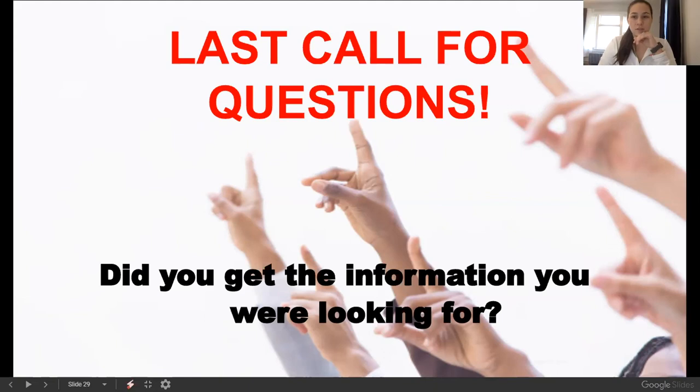We do look like we have one question so far. Have you experienced gas pressure loss in the winter? I had a job we did which had 7.5 inches and the boiler faulted in the middle of the winter. We rechecked and had 7.5 on static, but it dropped to 4.6 on high fire. It was about minus 35 degrees Fahrenheit.